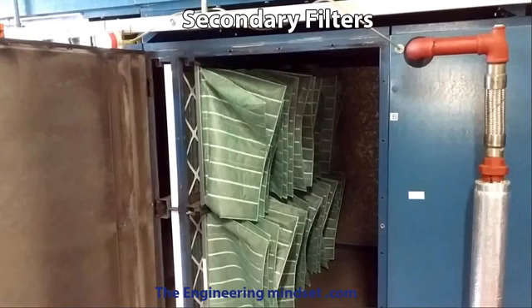Now the other filters which we're going to mention are the secondary filters, and they look a bit like this. These filters are there to catch pollen and bacteria and also some other dust which wasn't caught initially by the primary filters. Now these are typically a bag filter type made from a synthetic material, and as you can see they extend backwards a short distance and they will inflate a little as air passes through them, and that gives them a very large surface area. So you obviously got the surface area of this side and then on the other side of that as well, so we can capture a lot of air and a lot of particles in that air.